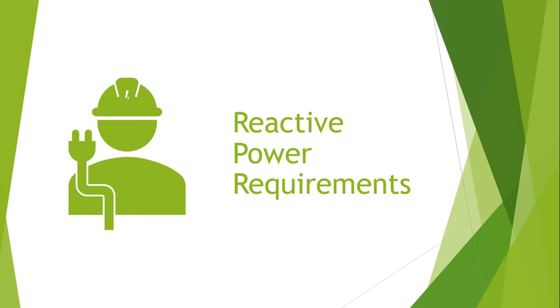We will continue with the reactive power requirement in an induction motor and induction generator. In an induction generator, the reactive power required to establish the air gap magnetic flux is provided by a capacitor bank connected to the machine in case of a standalone system. In case of grid connection, it draws reactive power from the grid to maintain its air gap flux.